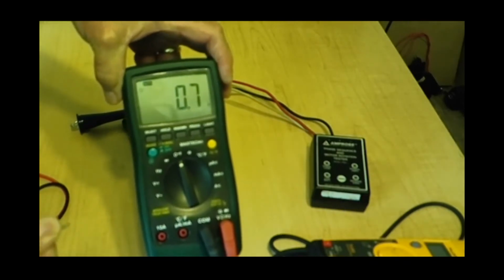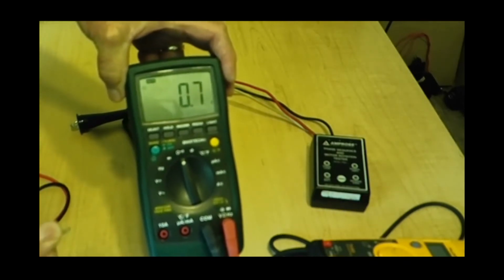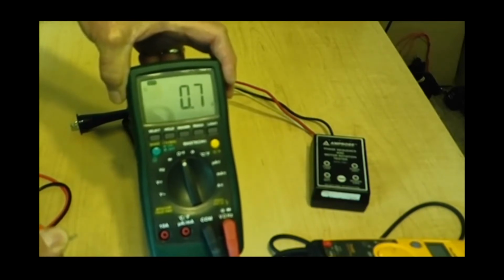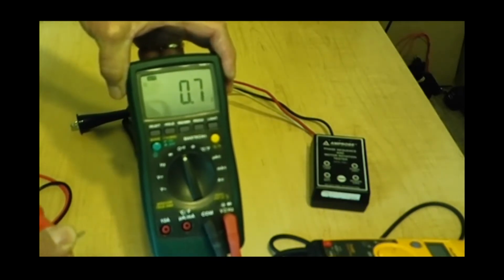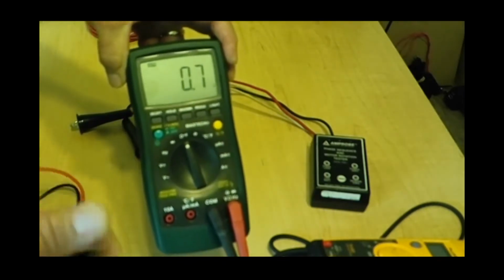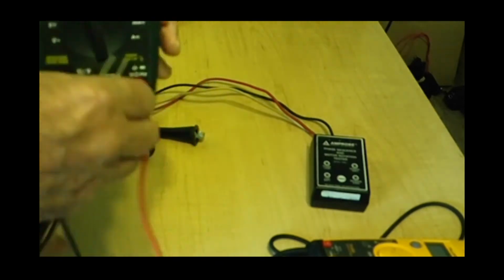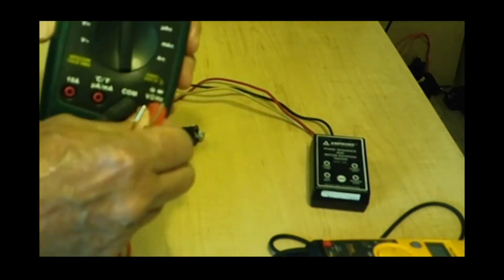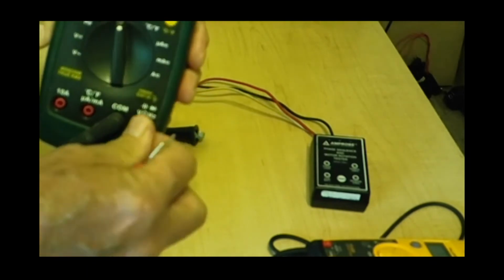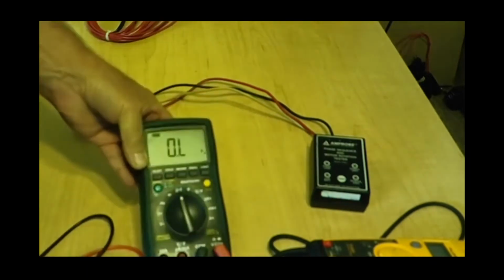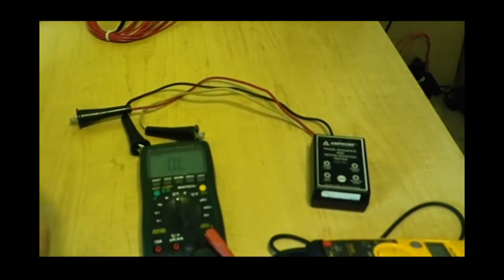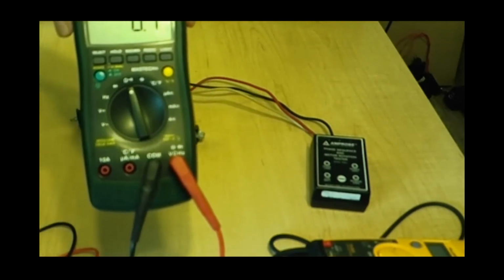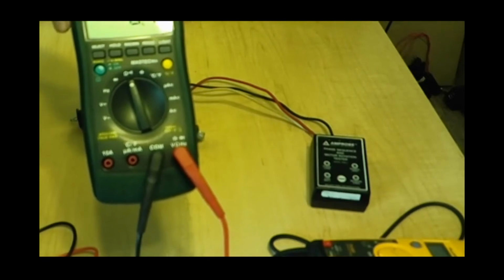I'm getting a resistance, 0.7. This is the resistance of the actual test leads, the wires. Now, we can do a couple things to fix this. We can wiggle the test leads and pull the test leads in and out. This normally reduces the resistance because they do get oxidation build up on those test leads. In this case, it didn't.